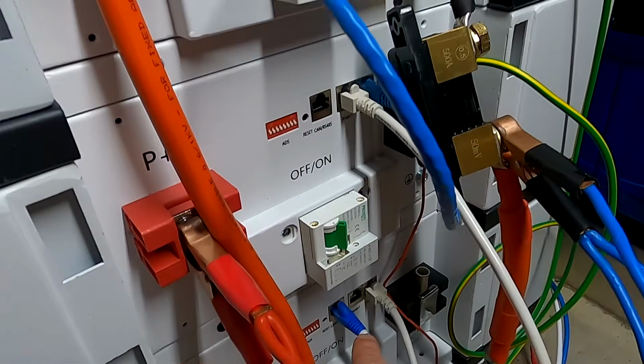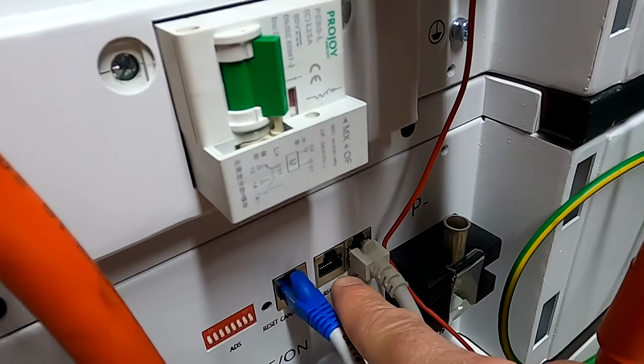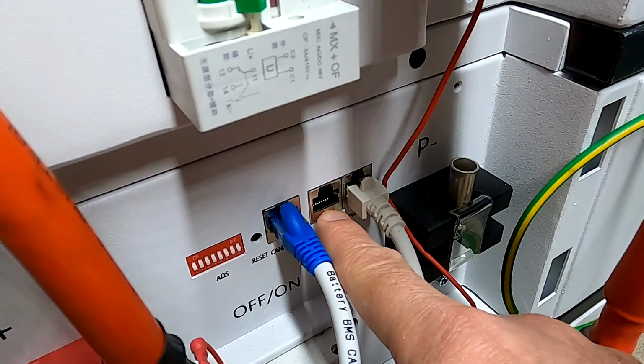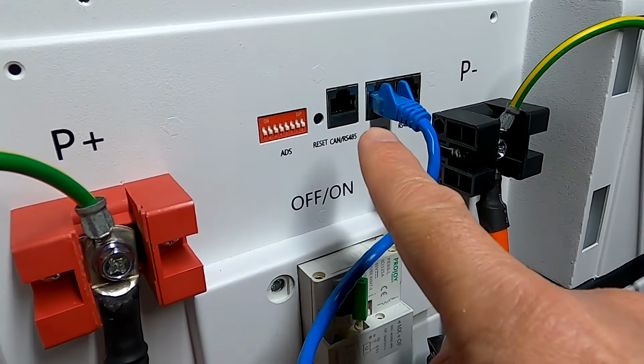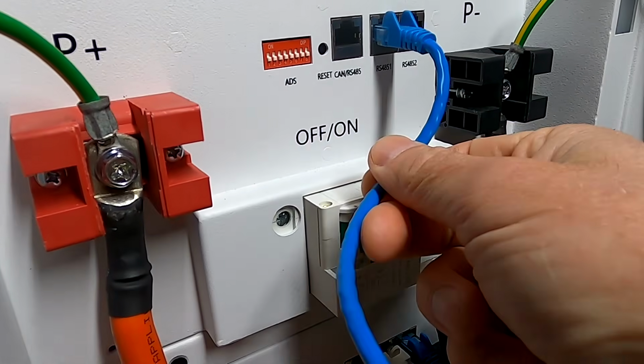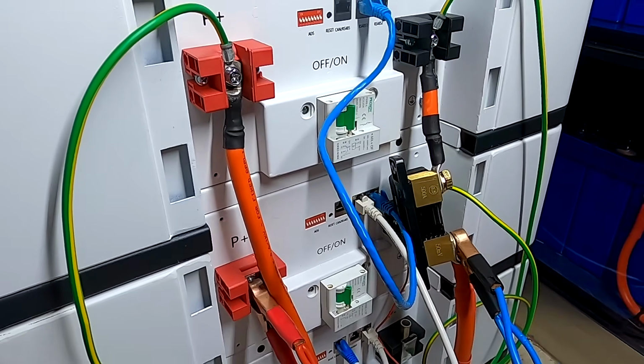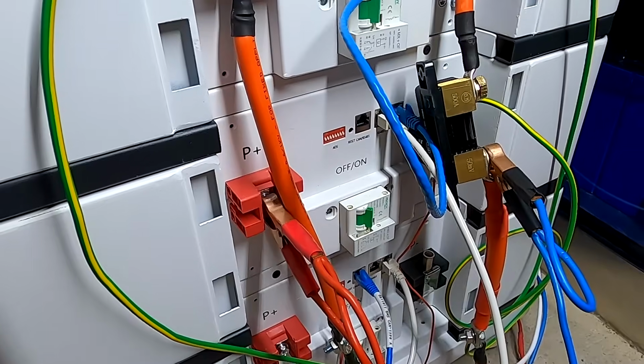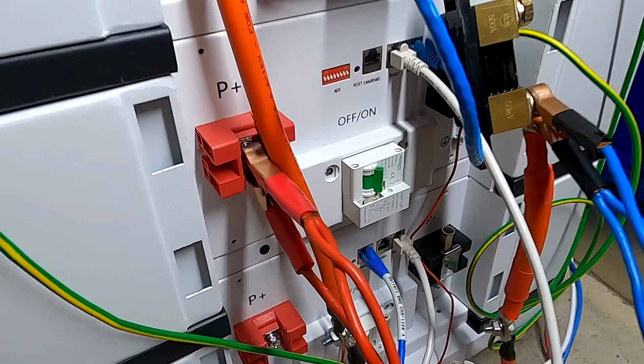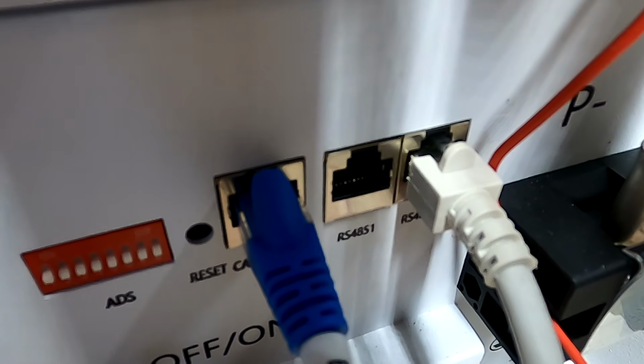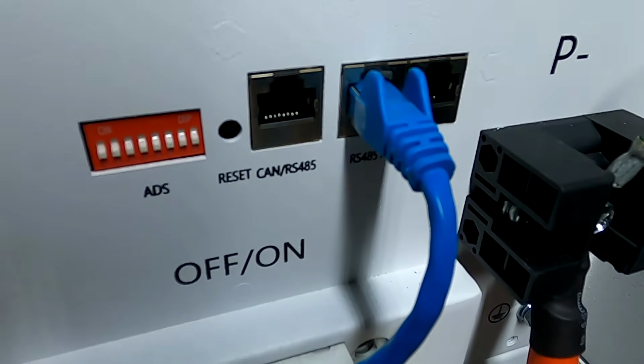So how does it know that this one is the master? The only difference is there's nothing plugged into port number 1. While here at the top, port number 1 is our communication port. So the master battery is determined by having nothing plugged into the first RS485 port.